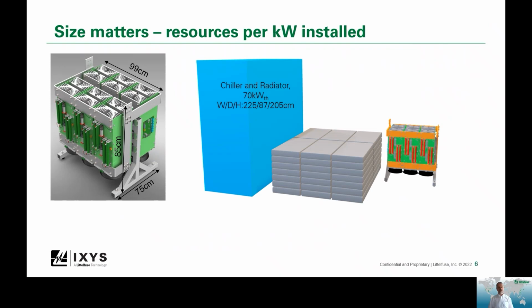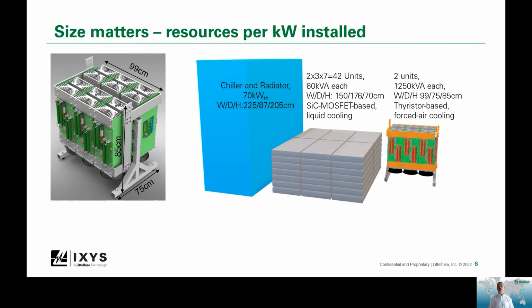With 97% efficiency and 2 megawatts of throughput, something like 60 kilowatts of losses need to be dissipated, which demands quite a huge chiller, represented by the blue block. This chiller can transfer 70 kilowatts of thermal power, but it demands 20 kilowatts of electricity to do so. The sum of devices at 60 kilowatts to support a more than 2 megawatt unit means there are 42 units to be paralleled, which leads to 84 connections for tubes and the same number of screws for the electric connection. In contrast, a single unit in one stack formed from 2 B6 topologies is all it needs to convert the power. And to scale, the silicon carbide-based solution of 42 units would consume as much as 6 cubic meters of space, while the thyristor-based approach only takes 10% of that. The factor for resources per kilowatt installed is massively better in the thyristor approach.